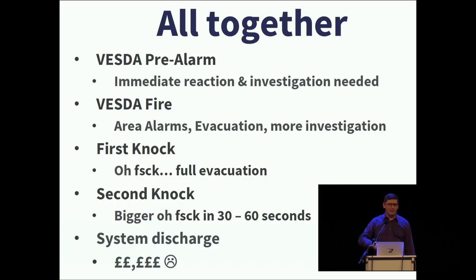So we put all of this together. You've got all your detection and all your alarming and your suppression system. So you've got your VESDA, and it's gone, oh, I've seen a pre-alarm. So we've got to immediately respond to that. Jumps into fire. Oh, that's not a great situation, but okay, get the building evacuated, have your fire marshals go and check everything out. You get to a first knock, that means one of your detector heads has detected something like smoke, and then you're like, okay, this is kind of getting serious. A second knock will then generally activate your fire suppression system. In between 30 and 60 seconds, whatever suppression system you've got is going to start discharging.